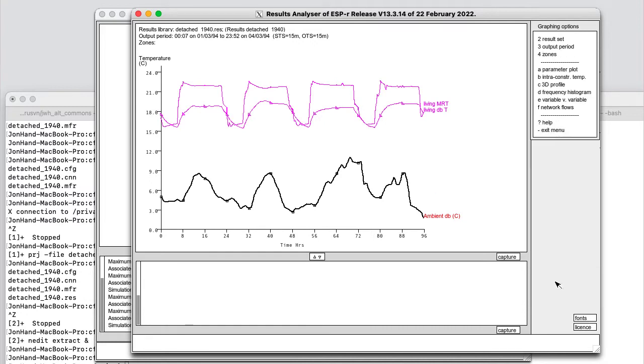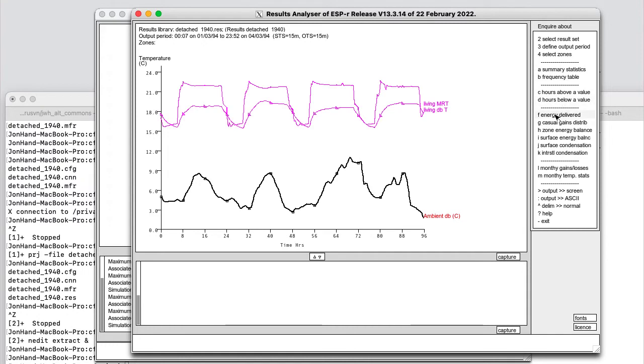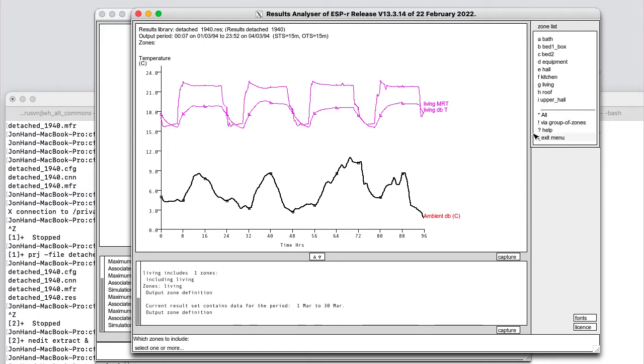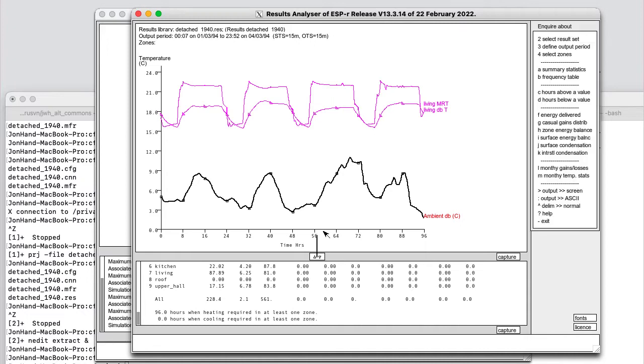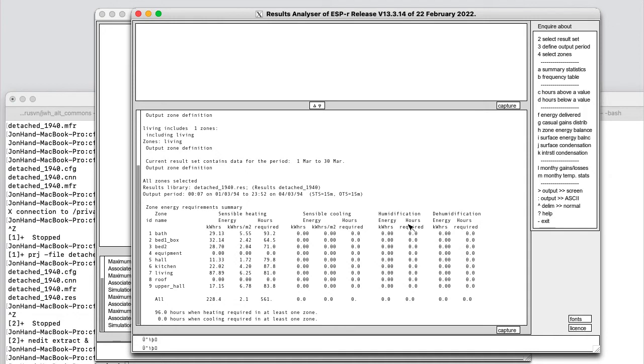Graphs are one area, but there are all kinds of reports that are available in ESP. For example, we can inquire about energy delivered. If we choose that for all of the zones, we get a very classic report in ESP. It talks about, for each of the zones, the sensible heating, the sensible cooling, and humidification dehumidification. Now, I have no controls at the moment related to humidification or dehumidification, so I will probably want to remove that from any report going to the client. In terms of sensible heating, we've got in kilowatt hours, kilowatt hours per square meter, and hours required.